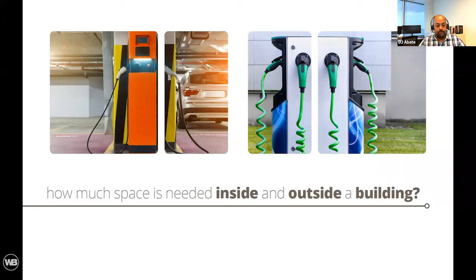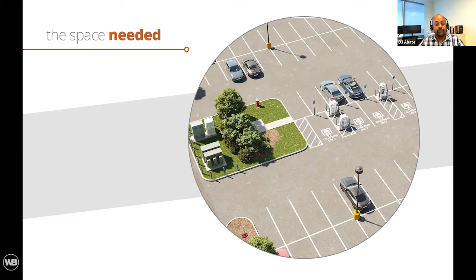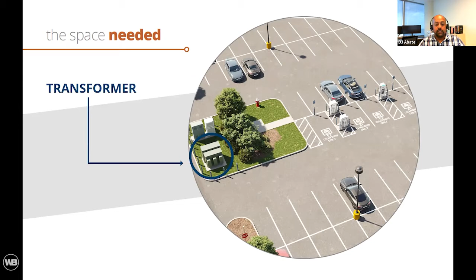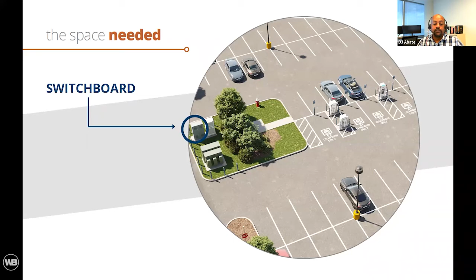We have a rendering here that we created for one of our clients that has 3 level 3 dual charging stations. In this scenario, we had to bring in a new electrical service, so we had to find a location for the transformer, which is located on the island there, and just above the transformer is the switchboard. In this one, we had 3 charging stations, and the switchboard was about 6 feet wide. For every 3 to 4 charging stations added, the switchboard equipment would grow by another 3 feet or so. Right next to the switchboard is the power unit that serves the charger.